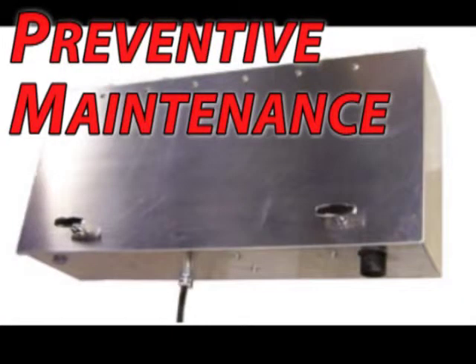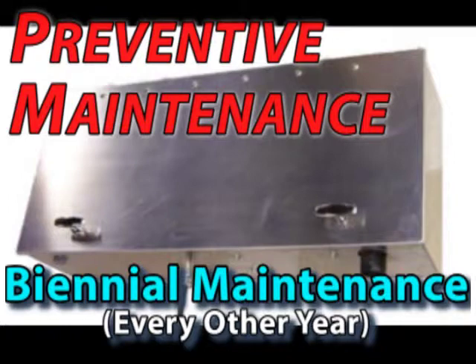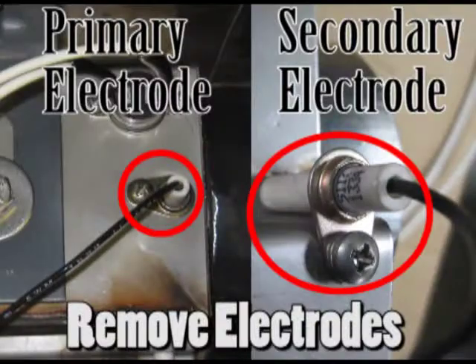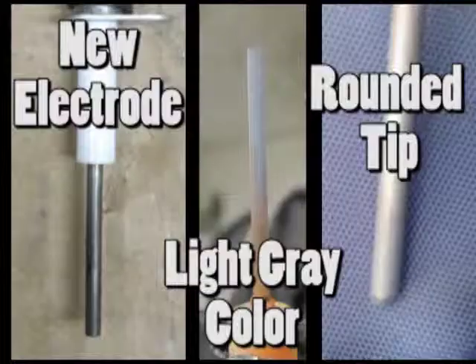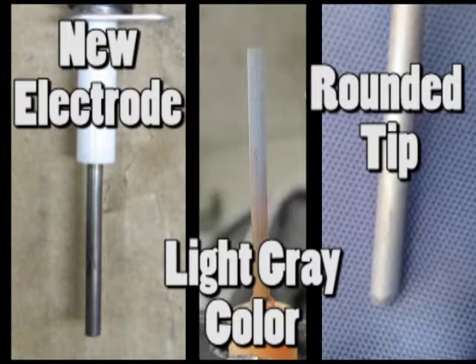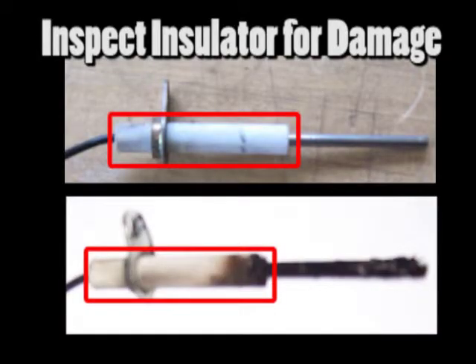In addition to the yearly maintenance just described, additional preventive maintenance, to be described in a few moments, should be done on an every other year schedule. Remove both spark electrodes and check for damage and deposits. The metal component of the electrode should not be any darker than a light gray or have an excessively rounded tip. Inspect the porcelain portion of the electrode for cracks and damage.